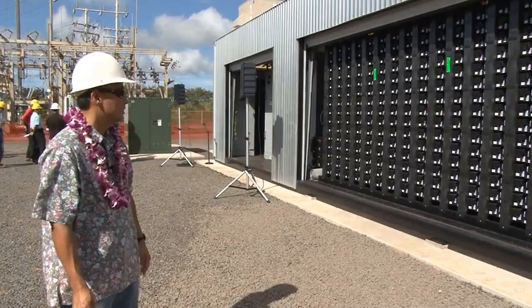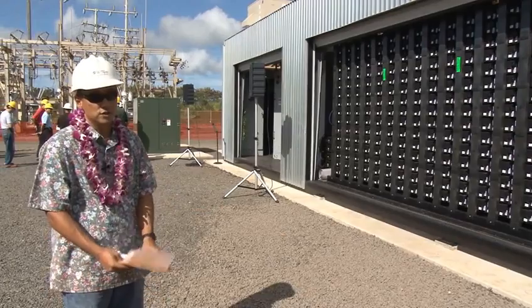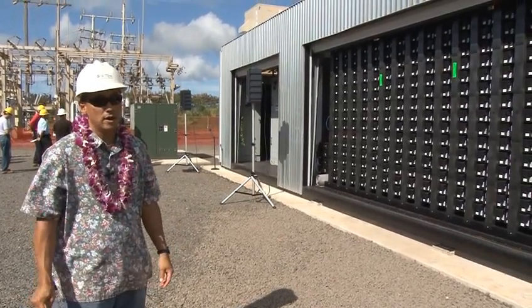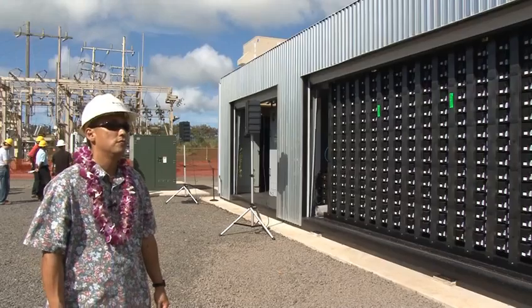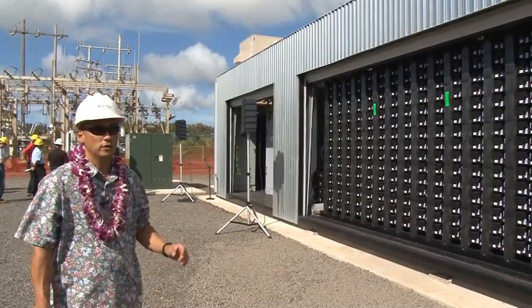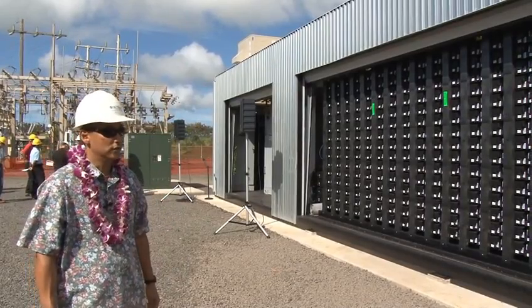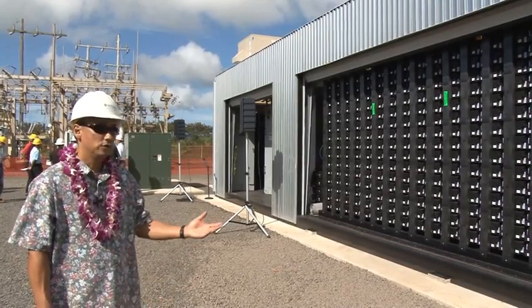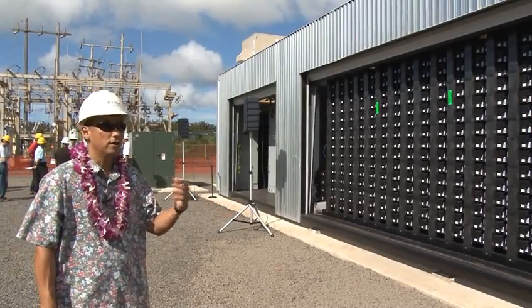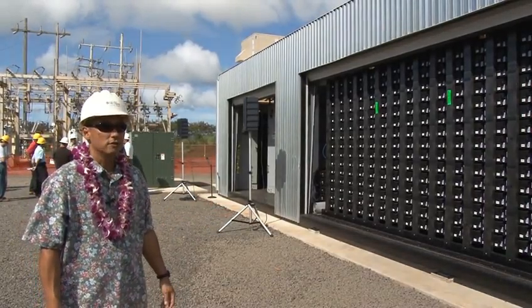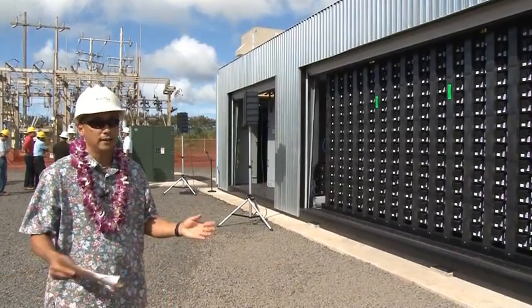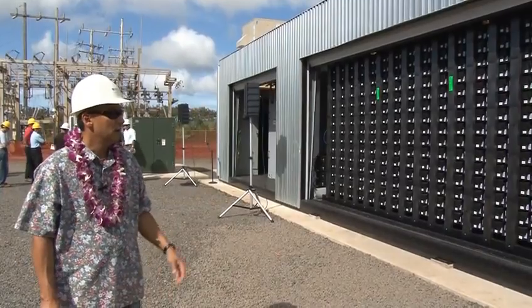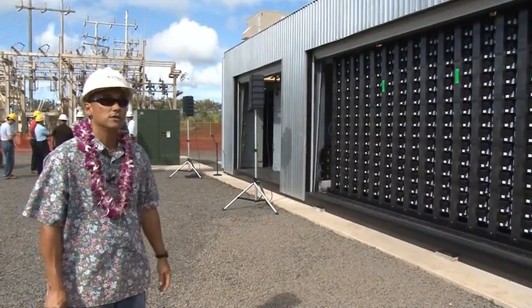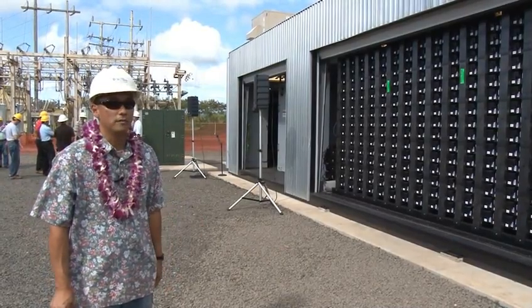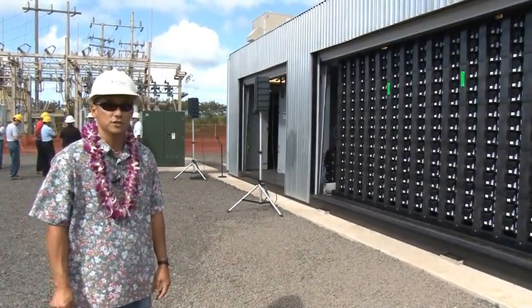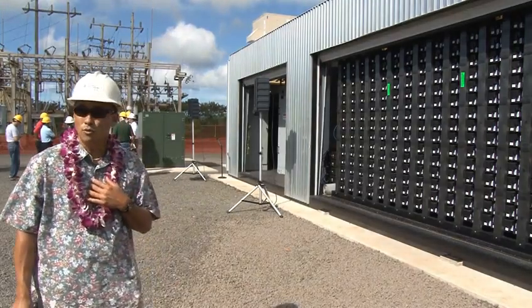It's very smart electronics in there. It can do a lot of other things. I mentioned that this was a 1.5 megawatt battery for 1 megawatt hour, but it also can do an overload rating of 2.25 megawatts for 10 seconds. It'll hold it for 10 seconds, and then it'll automatically drop to 1.5. So if you do the math and you get three of these at 2.25, you've got 6.75 megawatts. One of our diesel generators is about 7 megawatts. So if we lose that generator and we basically load shed the island, we lose parts of the island, and that's just the way it is being on an island grid. With three batteries on, it'll save the system, no outages. So great grid support above and beyond just the PV increasing penetration. That was one of the key reasons we felt that we needed to own the system.